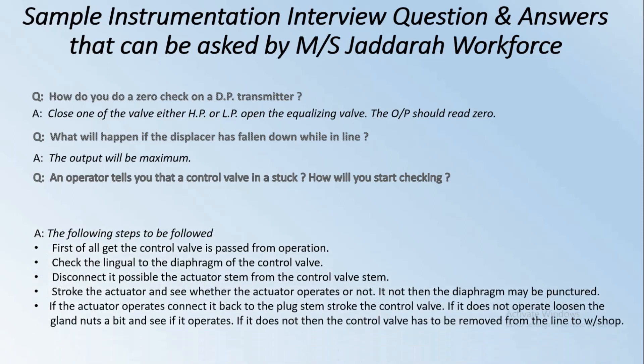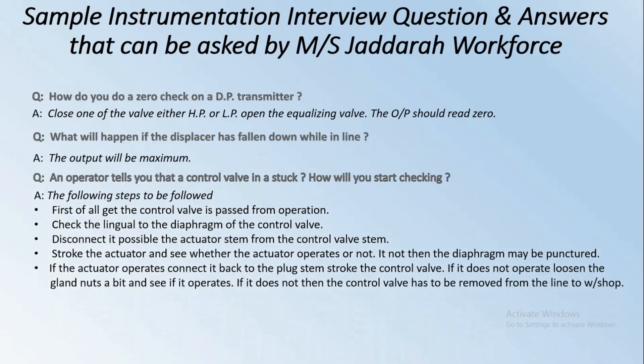Next: An operator tells you that a control valve is stuck — how will you start checking? First, get the control valve passed from operations. Check the signal going to the diaphragm of the control valve. Disconnect if possible the actuator stem from the control valve stem and stroke the actuator to see whether it operates. If not, the diaphragm may be punctured. If the actuator operates, reconnect it to the plug stem and stroke the control valve.